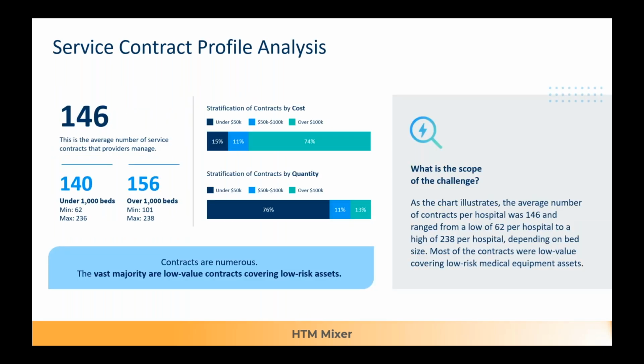So what we found: an average of 146 service contracts per hospital. You see there's not a lot of variation between those under 1,000 beds and over 1,000 beds, 16, not a huge variation. It ranged from a low of 62 per hospital to a high of 238. I think with the low of 62, you never know how well they're doing with that. You're not looking at the quality outcomes based on that. And 238 seems really high, but again, without looking at too much of the detail, it's hard to say whether those are good. But the vast majority of these are low value contracts covering low value, low risk assets. So again, look at the criticality of that asset, and at what it would cost to bring those things in-house. Does it make sense to have contracts on low risk, low dollar items?